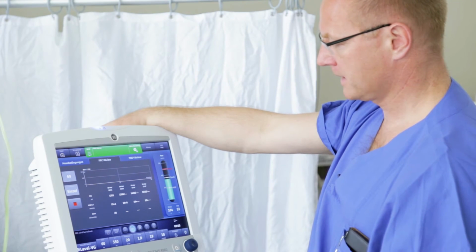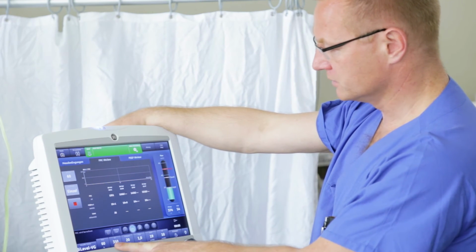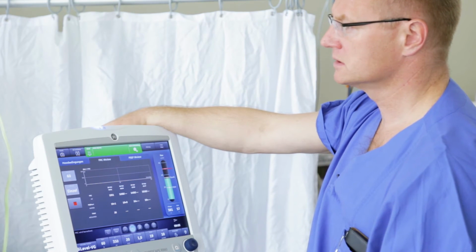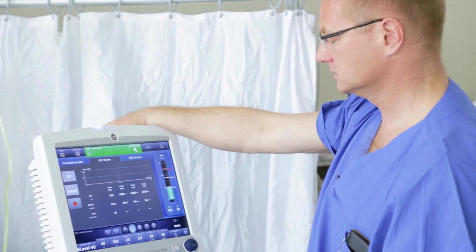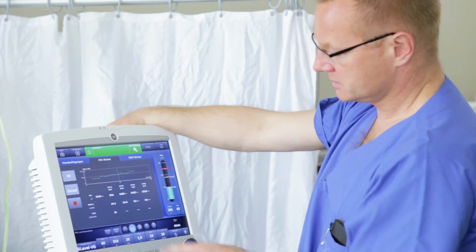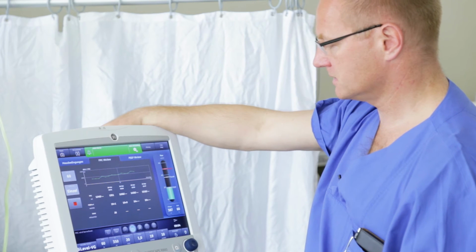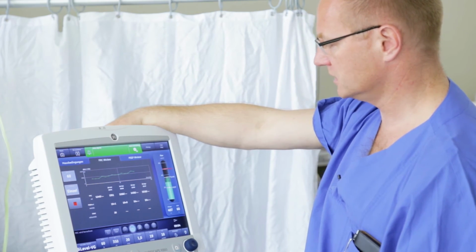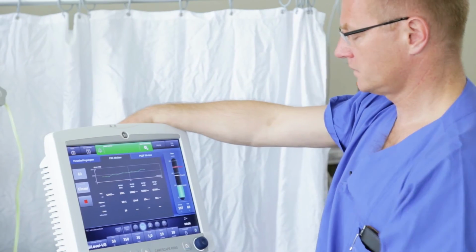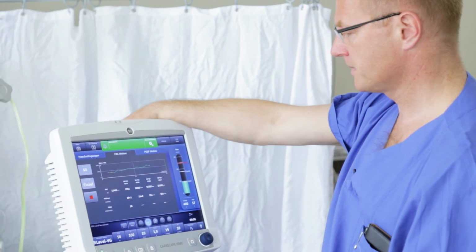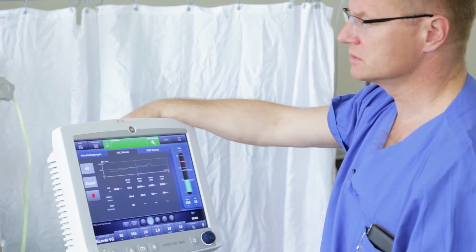The device has changed the inspiratory oxygen concentration from 50% to 60% so that the first measurement begins right away. And here we already have the first value. The inspiratory oxygen concentration is then reduced once more from 60% back to 50%. The inspiratory oxygen concentration is now at 50% again, so the second measurement cycle will begin immediately.